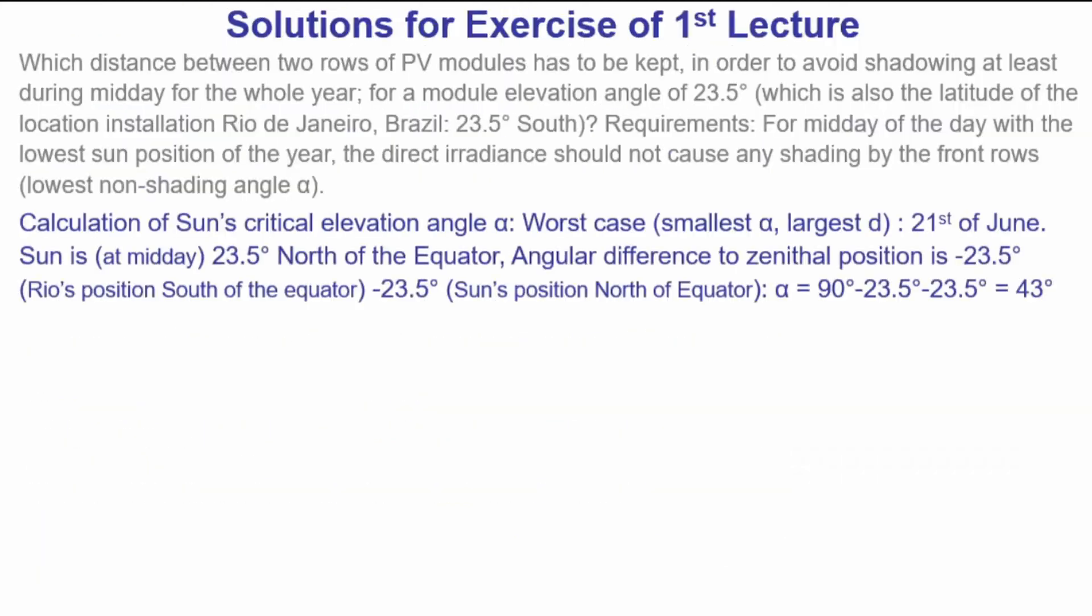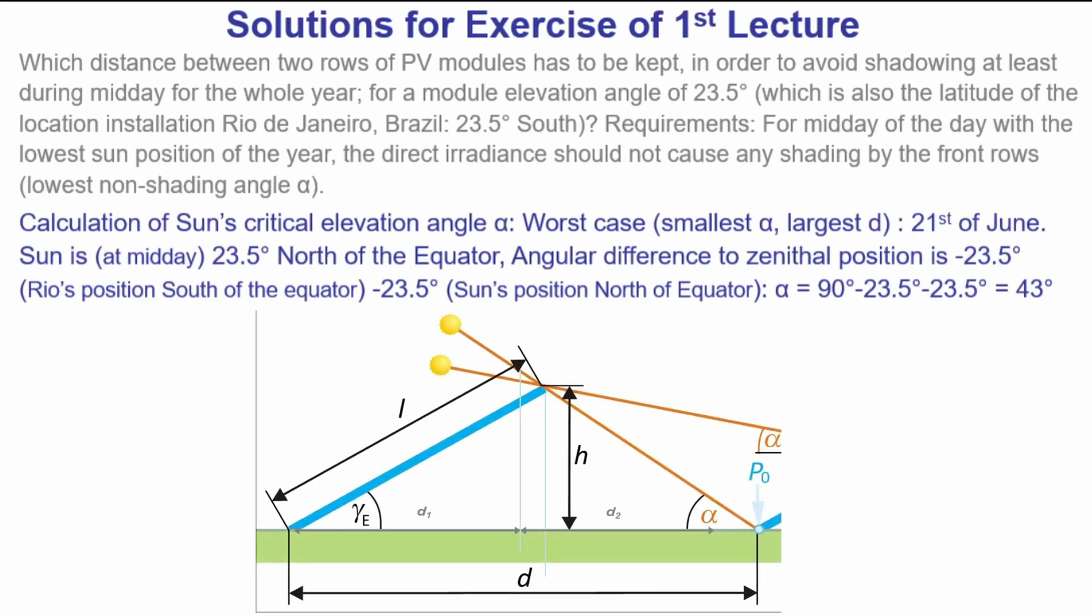So just to copy the gray part, we approach it like this. So we calculate the sun's critical elevation angle. This is worst case. That means we have the lowest elevation angle of the sun, which is then equivalent to the lowest or the smallest alpha angle. And this means that it is the largest distance between two rows. And for the southern hemisphere, this is the 21st of June.